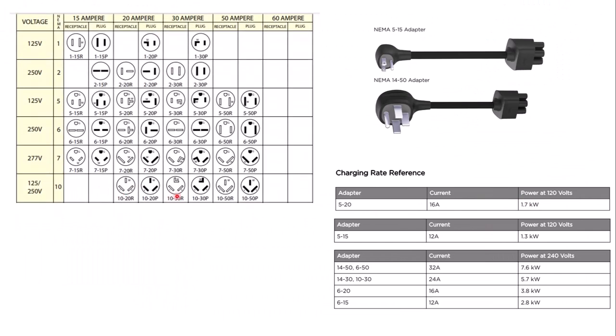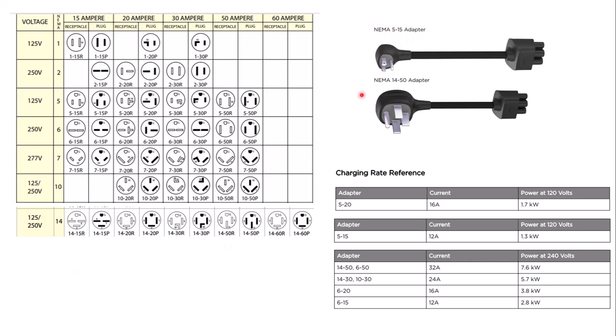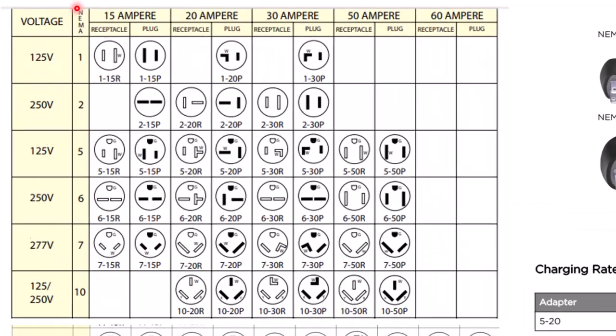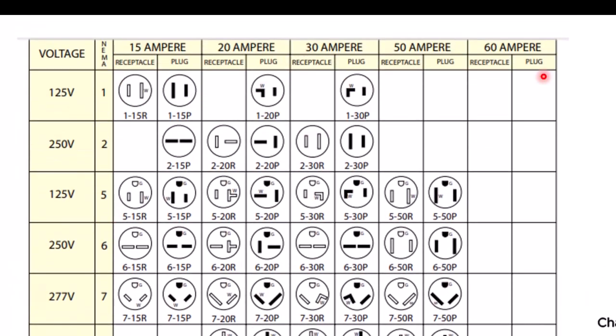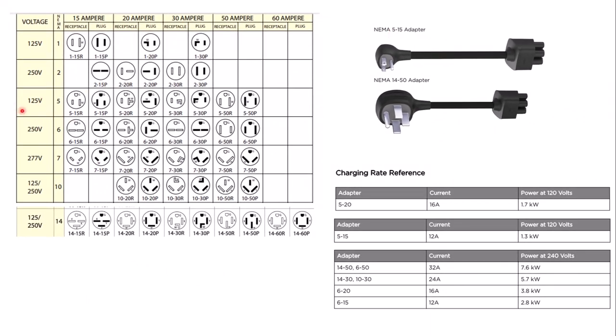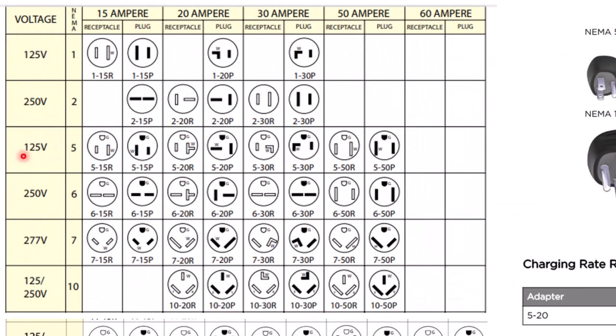So I'm just going to go over some of the NEMA ratings just so you kind of understand what they mean. So if you look on the left here, these are the charts for the different NEMA ratings. So the NEMA ratings are in this column right here. And you can see for the NEMA 5, it's basically right here. It's a 120 volt rating. And this is the standard receptacle that you see on walls that you plug standard appliances into. So those are basically the NEMA 5 rated. And you can see the R for receptacle, P for the plug. And this is generally what the NEMA 5 look like. And you can get in 15 or 20 amperes.